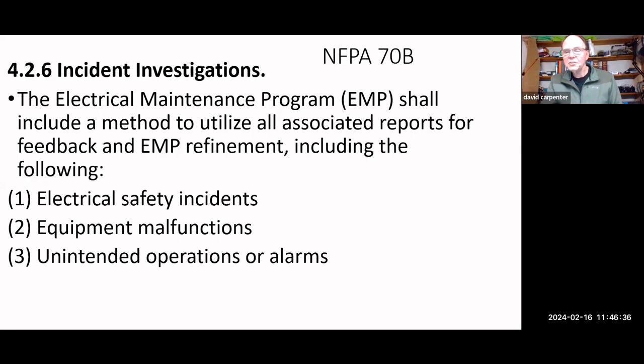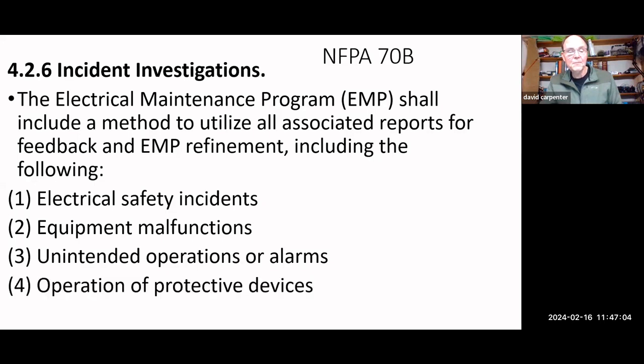And that could be even static. That's one of the problems with combustible dust plants. They don't report static electricity because they don't think it's all that valuable. It's very valuable. In fact, NFPA 77 is the static electricity standard. And NFPA spent the last 4 years doing research into how static electricity is causing several fires and explosions and actually deaths in some cases.